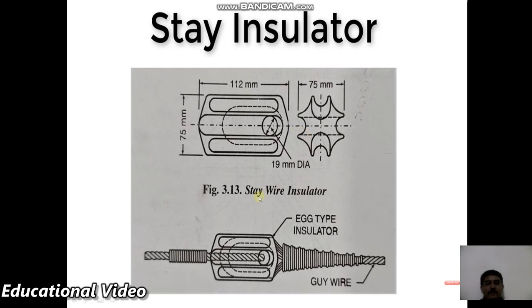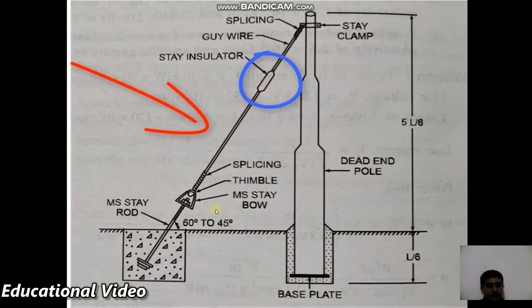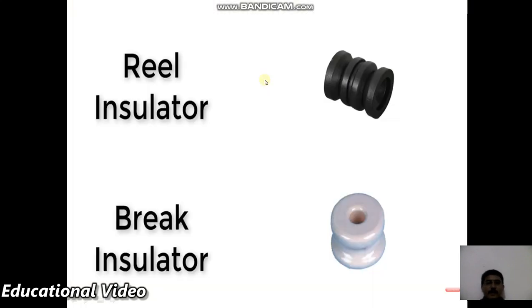The stay insulator, also called an egg type insulator, has no voltage present across it during normal working conditions. It is used to provide additional mechanical support to a pole to prevent bending when the line exerts lateral force. This stay wire mechanism keeps the pole stable under load.